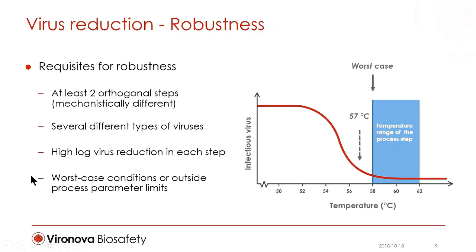To obtain a robust overall virus reduction, at least two mechanistically different virus-reducing steps should be tested. Each step should be tested with several different types of viruses. A virus reduction of at least four logs should be obtained in two or more steps. The testing should be done at the process parameter limit where virus survival is most likely. If a temperature span of 58 to 62 degrees is allowed, the testing should be performed at 58 degrees. This is called worst-case conditions.